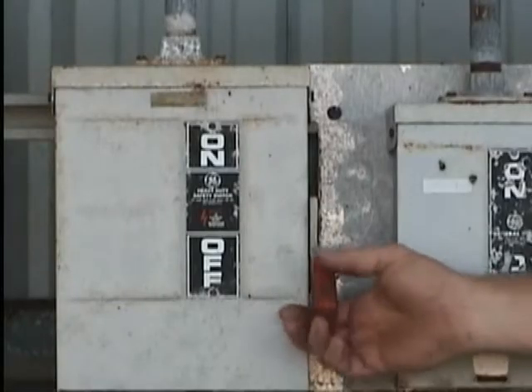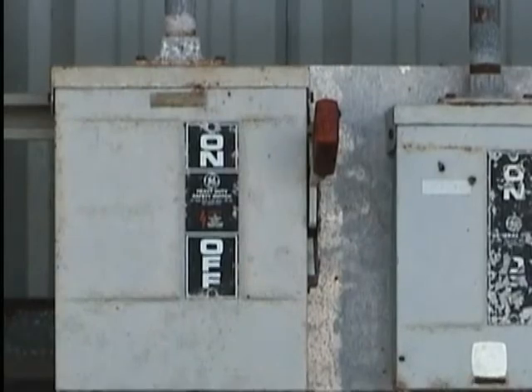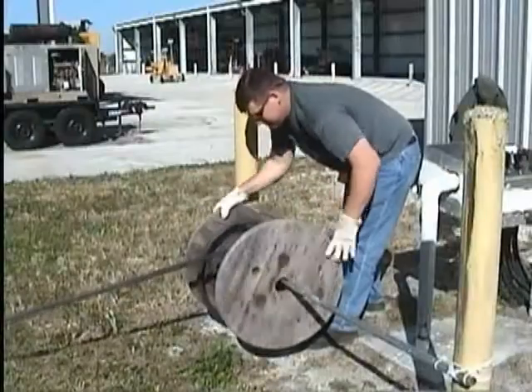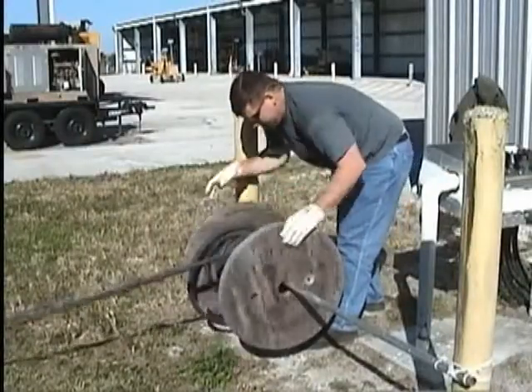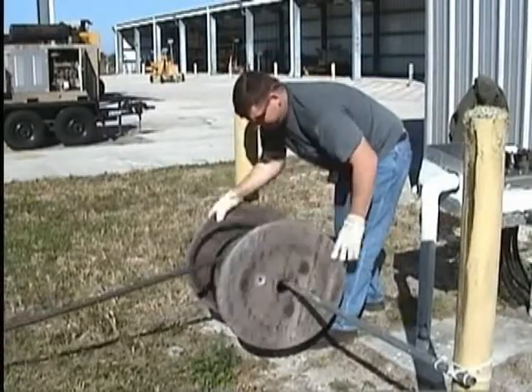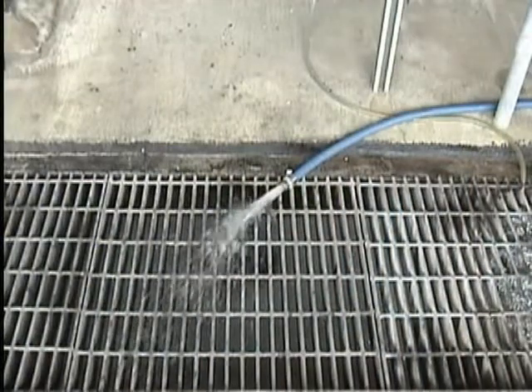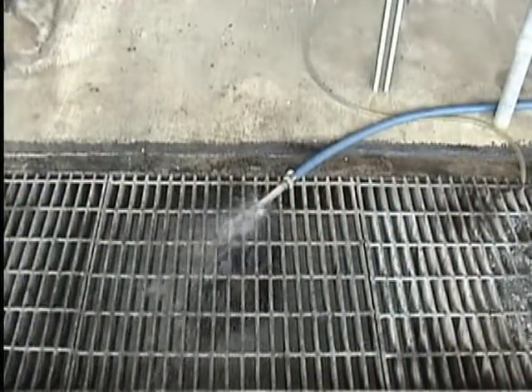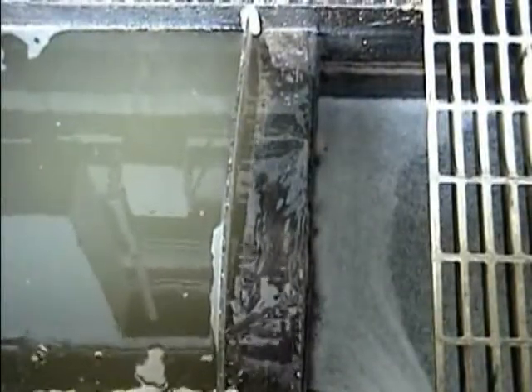The center accumulation sump wastewater circulation pump is then re-energized, and the circulation pump is used to pump the treated wastewater to the sanitary sewer lift station. After the sump has been drained, the pump is disconnected from the ROTOP and reconnected to the rock media filter. The ROTOP is retracted and stored on the storage reel. At this time, any wastewater that has been collected in the west collection sump is pumped to the east collection sump to begin the treatment process of that wastewater.